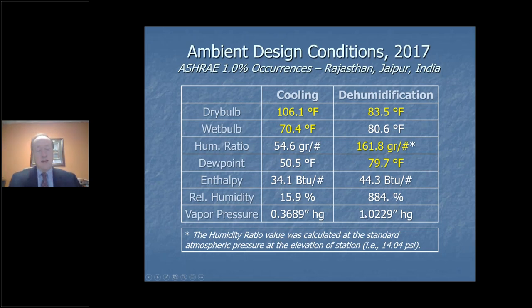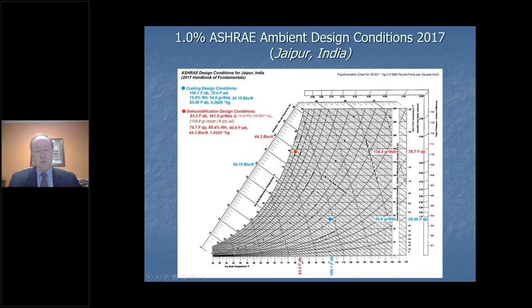That cooling design day that I just showed you on the chart, that would be this number right here. If you remember the psych chart looking like a pail of water, that's not a very high level of moisture. But when you look at that peak dew point or the peak dehumidification day, that's where that point is. Look at how much more moisture you would have at that. Now, I had one engineer tell me on a project several years ago, he said, well, I'm not too worried about that particular point. That doesn't happen all that often. Well, I pointed out that no, it happens the same percentage of time that that one does.